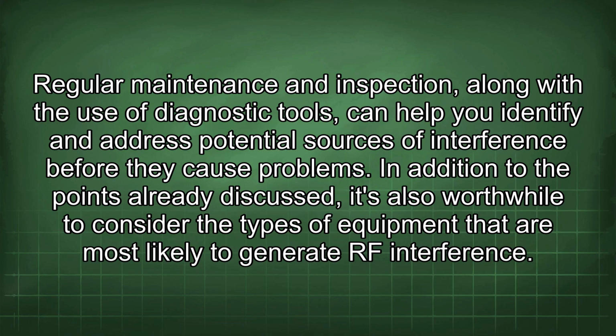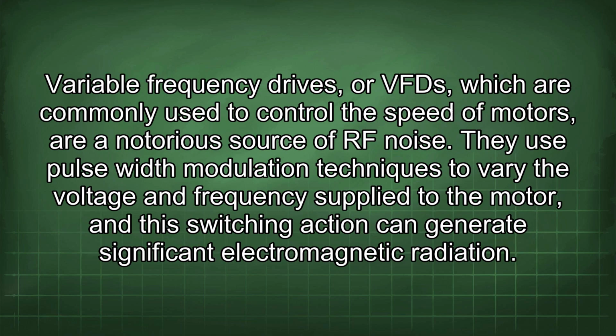In addition to the points already discussed, it's also worthwhile to consider the types of equipment that are most likely to generate RF interference. Variable frequency drives, or VFDs, which are commonly used to control the speed of motors, are a notorious source of RF noise. They use pulse width modulation techniques to vary the voltage and frequency supplied to the motor, and this switching action can generate significant electromagnetic radiation.